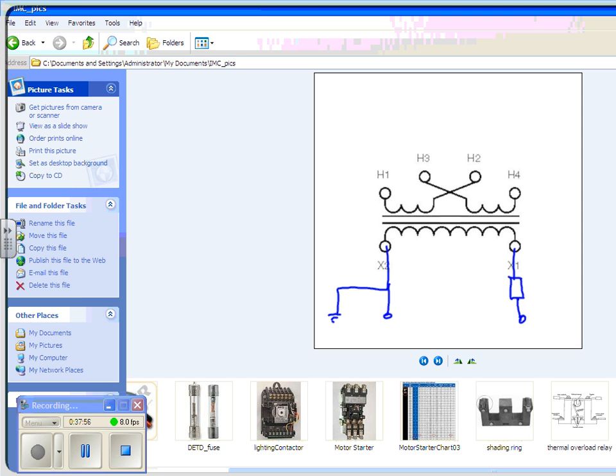And if I get to choose how this thing's going to be installed, and usually I'm going to get to choose, I'm going to select one with a control transformer. I don't want a different circuit in there because I've got to remember to go turn off that light circuit to make sure that my control circuit is dead when I go to troubleshoot it. If I put my ohm meter on a 120 volt lighting circuit, what will happen to my meter? It might let all the smoke out. And that's my meter, or at least it's the one assigned to me. And now that it's blown, I've got to go get a fuse. Now I'm not very happy.